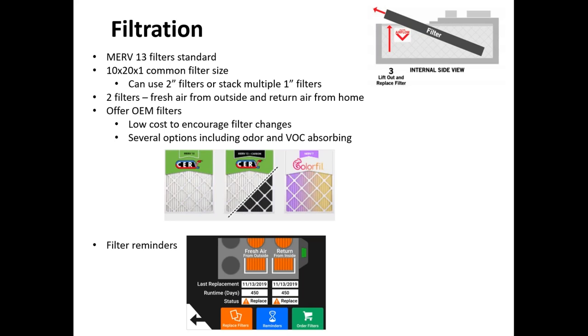So we also offer odor and VOC absorbing filters, both carbon, as well as a special one called Colorfil that changes color as it absorbs these pollutants. The filter reminders are a newer feature that is incorporated, so the system will automatically let you know when it's time to change. You can keep track either by runtime or by date, and these can differ as well. So the fresh air filter, generally it's a lot dirtier outside, and so that may need to be changed monthly as opposed to maybe every couple months for the return air filter. So these let you gauge things over time and make adjustments for these reminders.